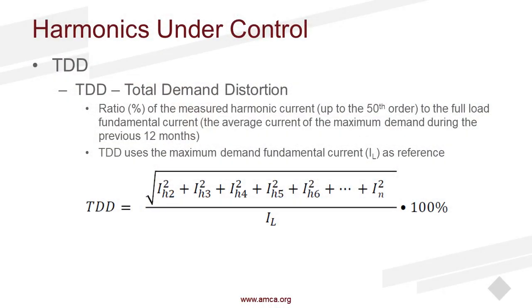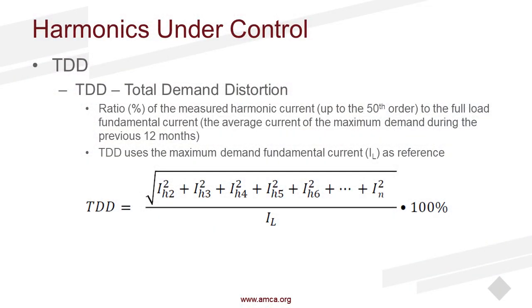And then we have TDD, our total demand distortion. This is the ratio of your measured harmonics up to the 50th order. Typically, we're looking at the 50th order. There are cases where you'll see harmonics at a greater order, but usually you can get the majority of that information from the 50th order, to the full load fundamental current, which is usually looking at a 12-month period and what the average of that current is, right? So your full load, the total on your system. And you can see that this formula looks very similar to THDI, but now we're looking at a different ratio with the full load current.